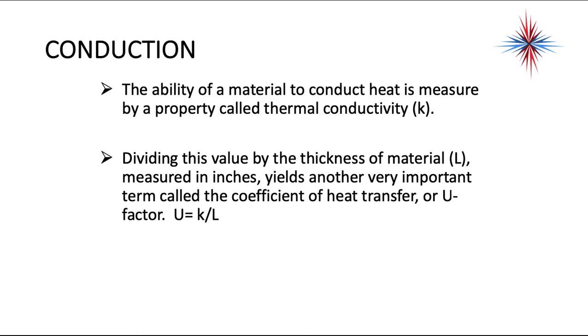The ability of a material to conduct heat is measured by a property called thermal conductivity, or K. Dividing this value by the thickness of the material, which is referenced as L in the formulas, measured in inches, yields another very important term called the coefficient of heat transfer, or the U factor. If you remember anything about this small portion of design, remember what a U factor is. It's the thermal conductivity divided by the thickness of the material. This becomes very important when we start talking about design.